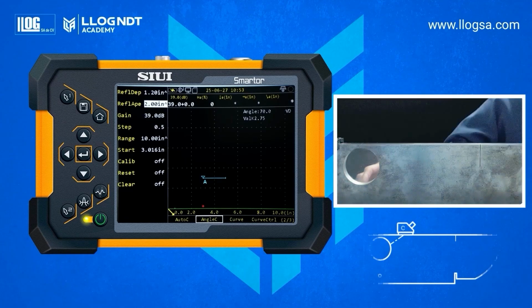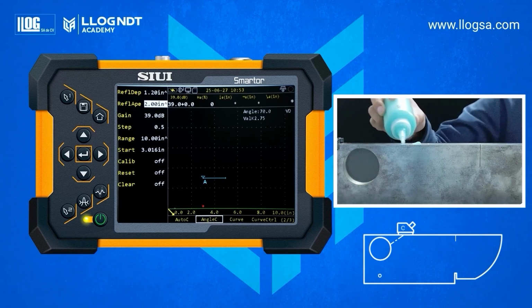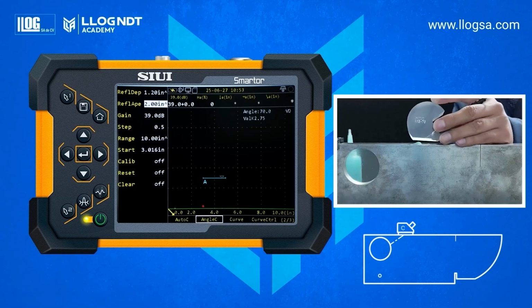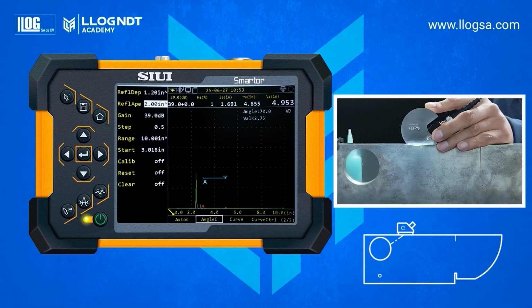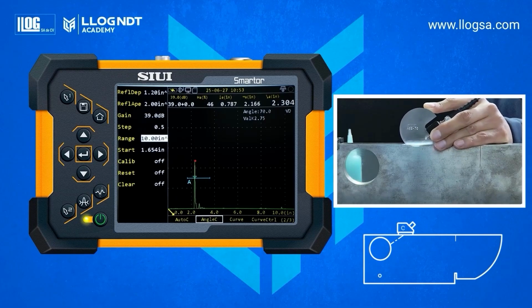Place the transducer in position B for angles from 40 to 60 degrees, or in position C for angles from 60 to 70 degrees. For this example, we will use a 70-degree angle, so we place the transducer in position C, aligned with the 70-degree mark, facing the hole with a diameter of 2 inches and a depth of 1.2 inches. Move the transducer back and forth until you find the maximum echo amplitude. Once the maximum amplitude is found, go to the Calibrate option. And confirm by pressing Enter to save the angle.